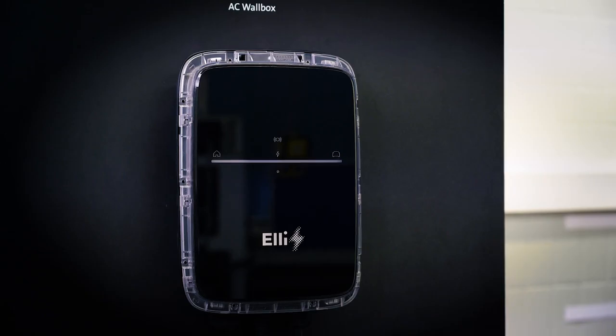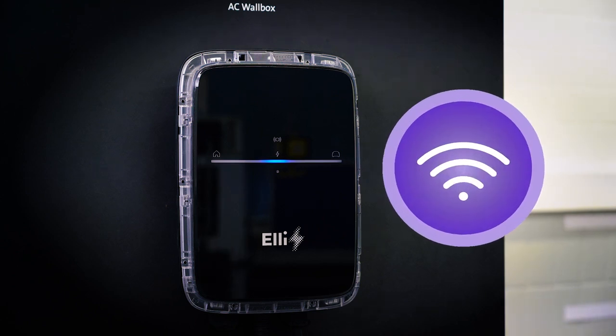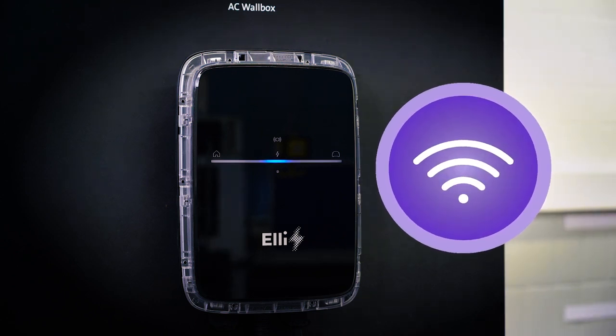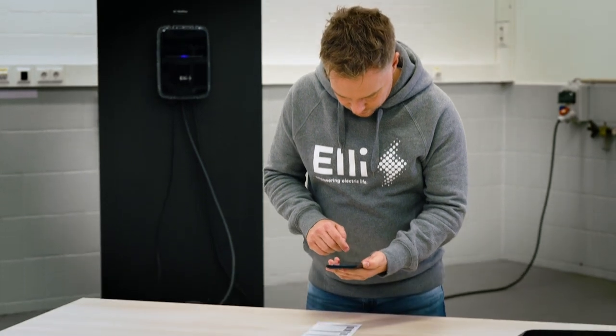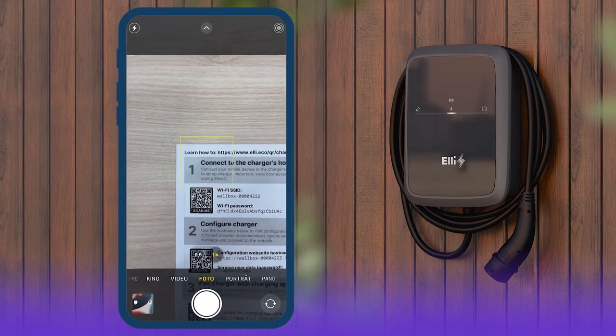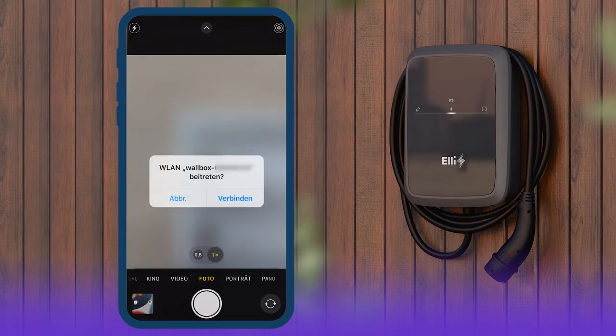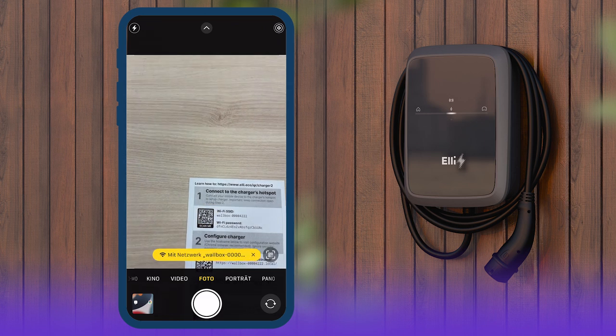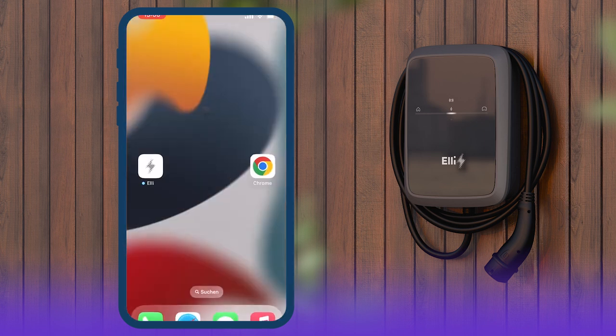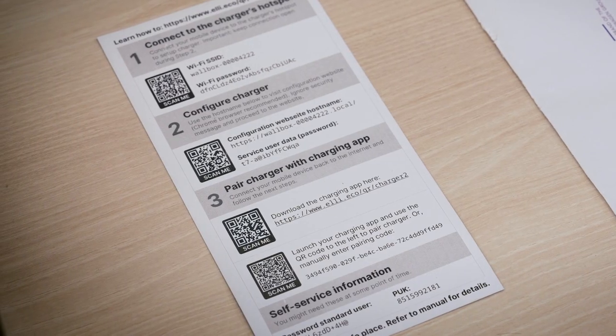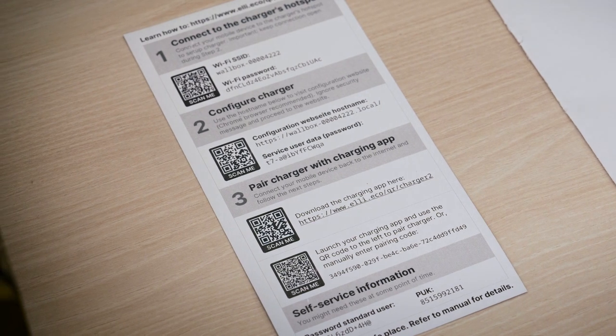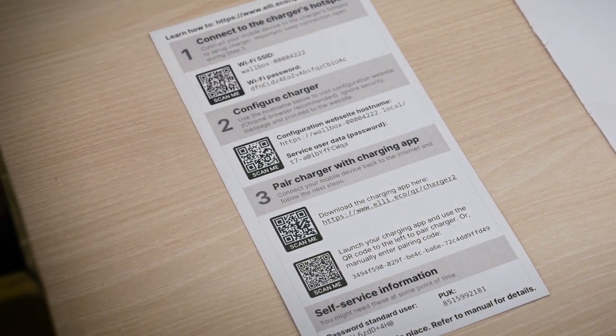Switch on the power supply. After the self-test, the Elli Charger 2's blue pulsating LEDs indicate readiness for configuration. The Elli Charger 2 generates its own Wi-Fi signal. Scan the QR code on the access card to connect your tablet or smartphone to the wall box. If this fails, or if you are using a laptop, connect manually. The SSID and password for the network can be found on the access data card.